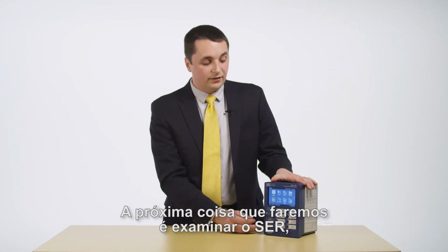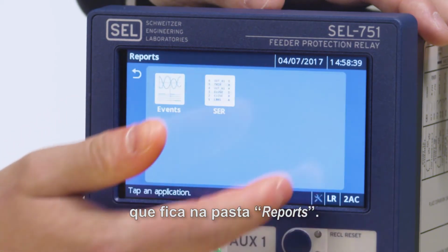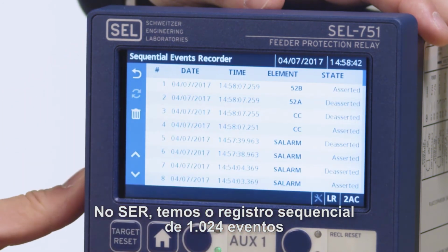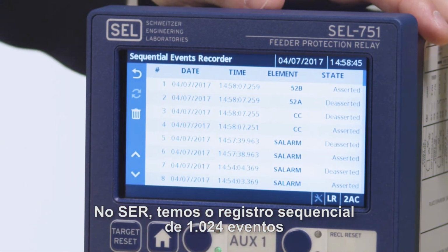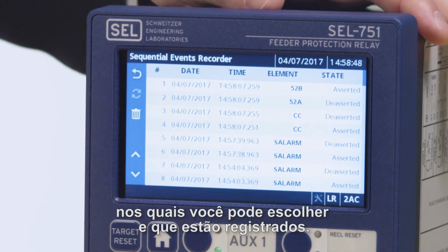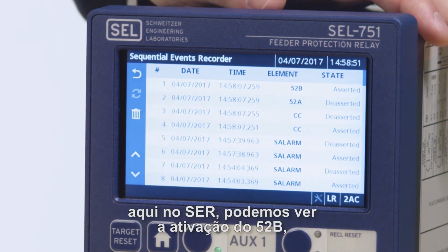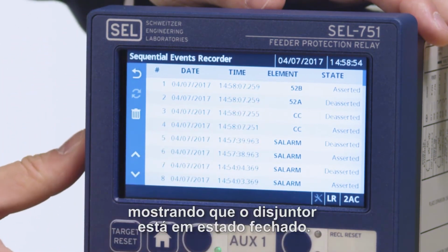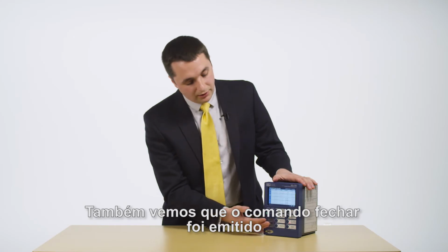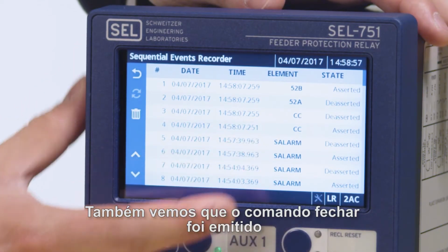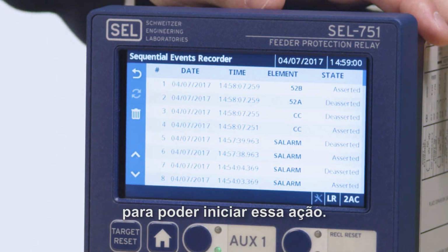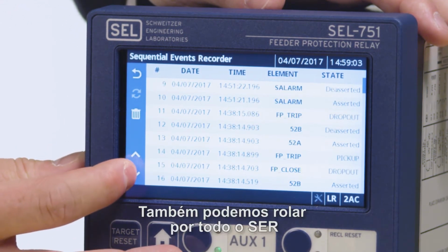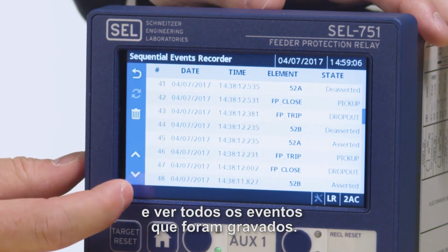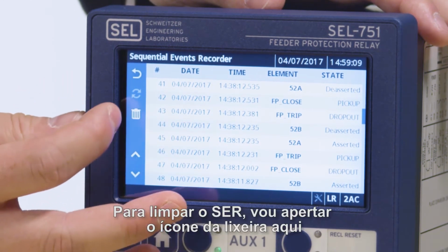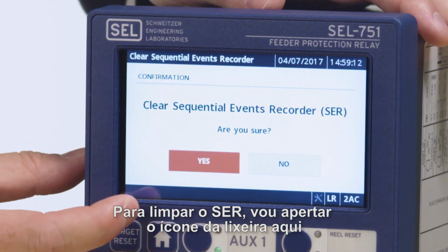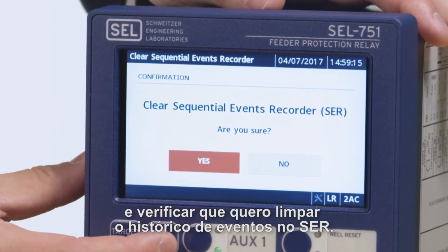The next thing we're going to take a look at is the SER, which is in the reports folder. In the SER, it logs up to 1,024 SER items that you can choose what is logged. Here in the SER, we can see that the 52B asserted, which shows that the breaker is in a closed state. We can also see the close command was issued to be able to initiate that action. We can also scroll through the SER and see all of the events that have been recorded.